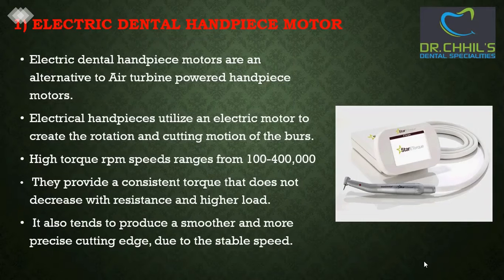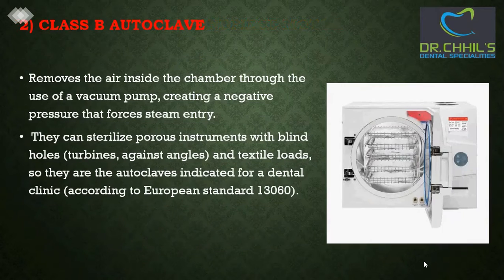Electric dental handpiece motors are an alternative to air turbine powered handpieces motors. Electric handpieces utilize an electric motor to create the rotation and cutting motion of the burrs. High torque RPM speed ranges from 100 to 4 lakh. They provide a consistent torque that does not decrease with resistance and higher load. It also tends to produce a smoother and more precise cutting edge due to the stable speed.